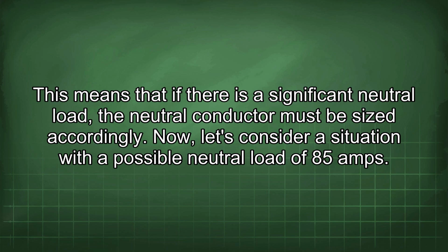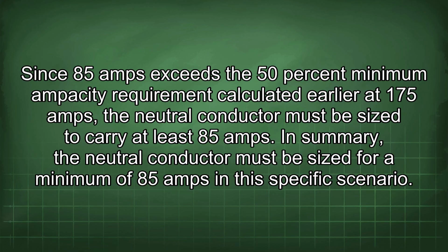Now let's consider a situation with a possible neutral load of 85 amps. Since 85 amps exceeds the 50% minimum ampacity requirement calculated earlier at 175 amps, the neutral conductor must be sized to carry at least 85 amps. In summary, the neutral conductor must be sized for a minimum of 85 amps in this specific scenario.